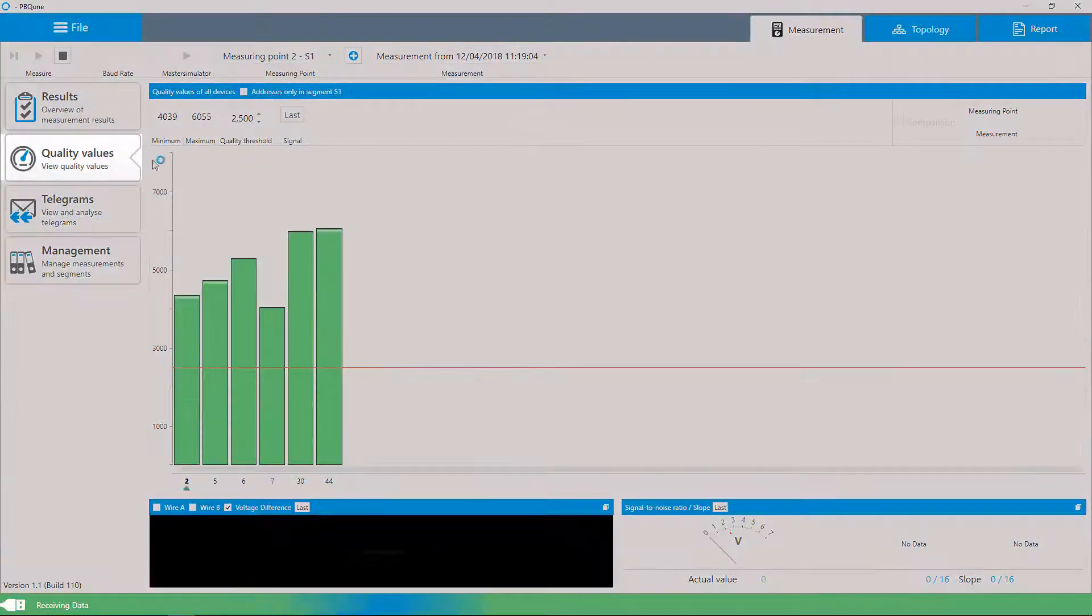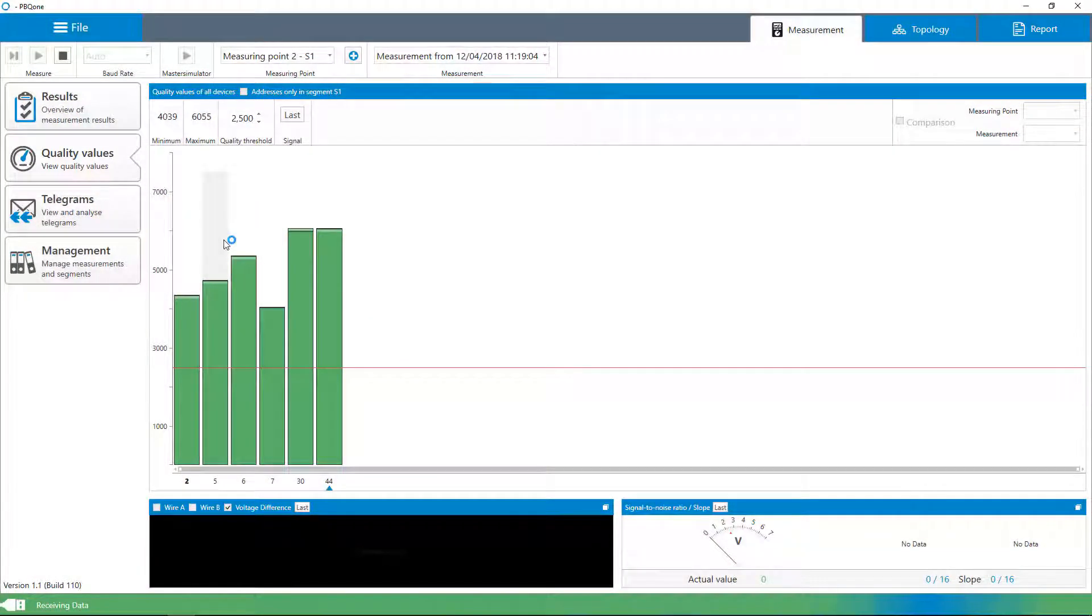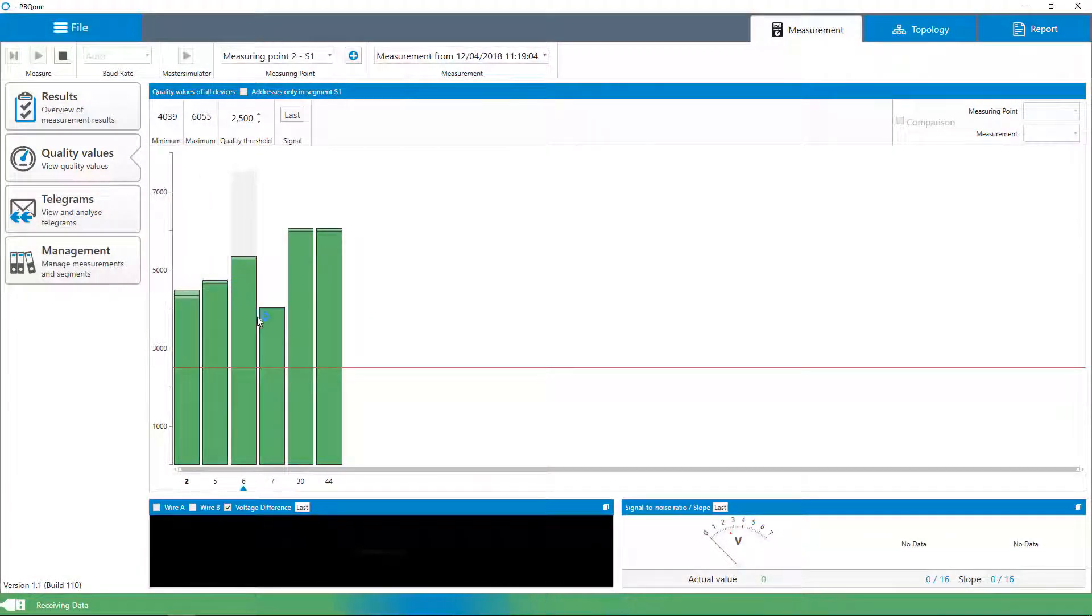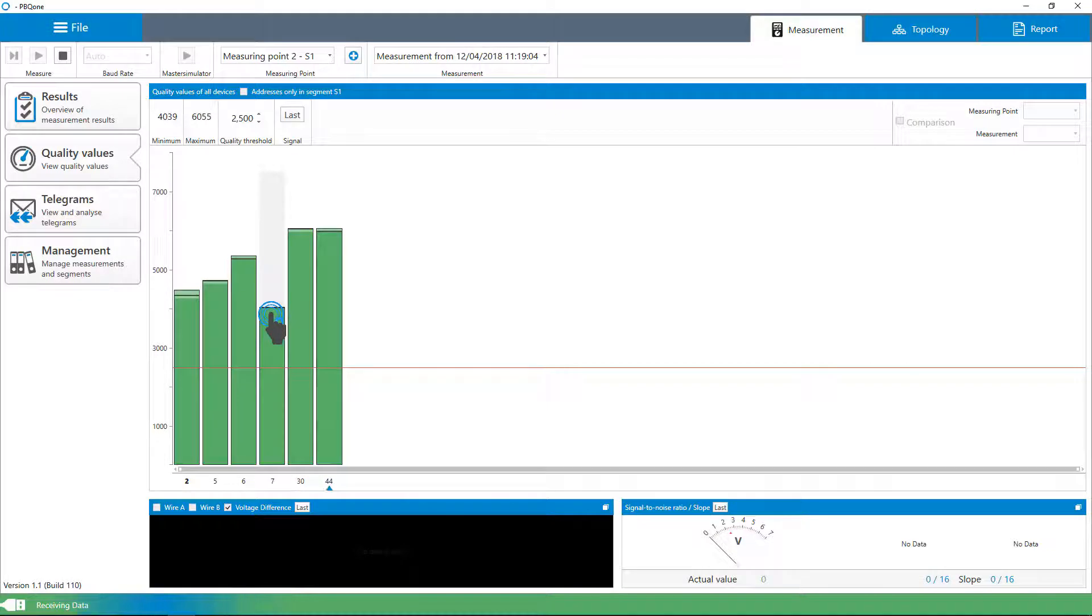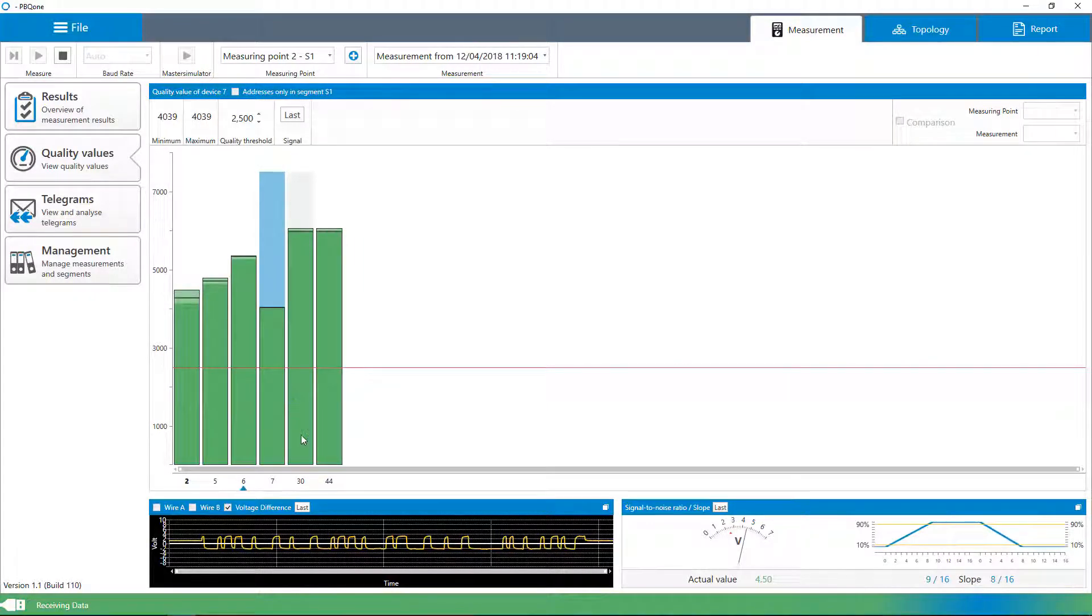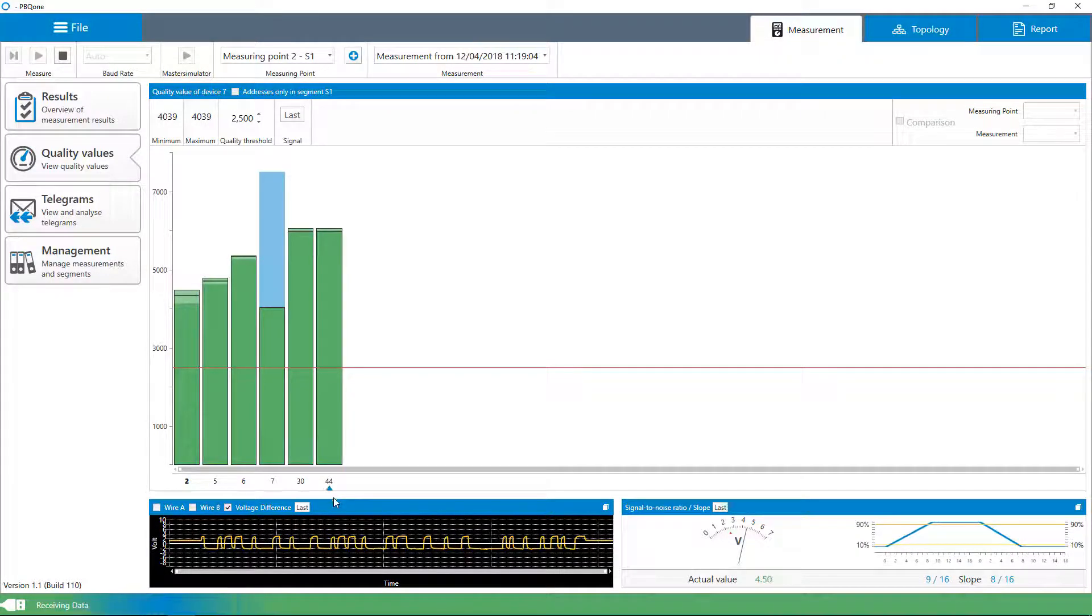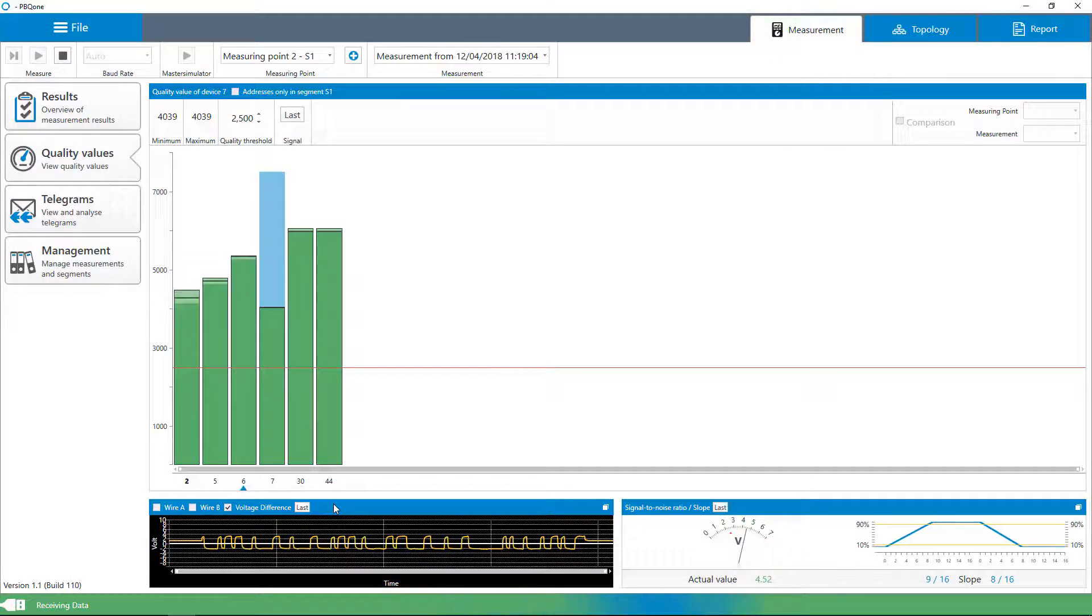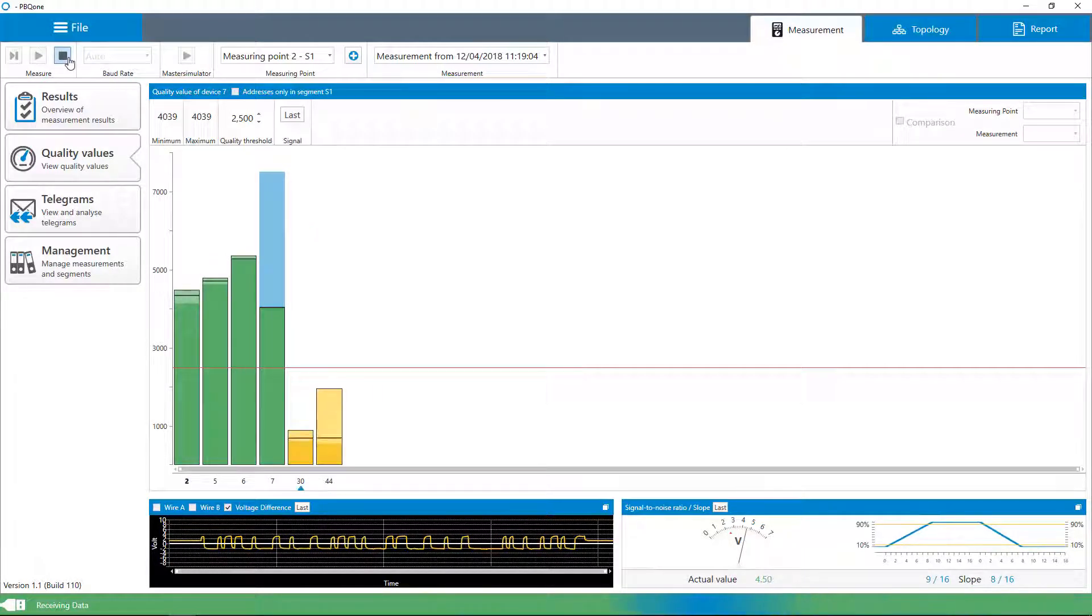The physical diagnostic results are displayed by means of colored measuring value bars. The size of the bars reflects the quality value that results from the currently measured differential voltage, edge steepness and transient response. If a bar does not reach the specified quality value threshold, the affected devices are displayed in yellow.